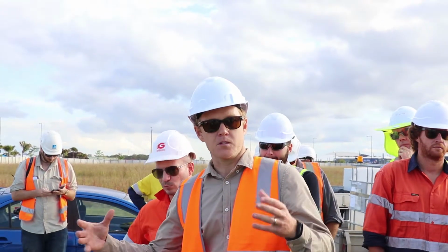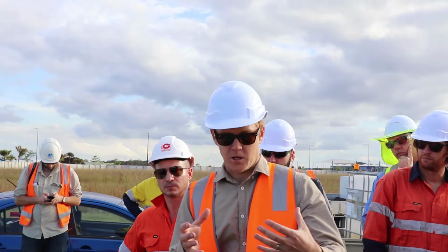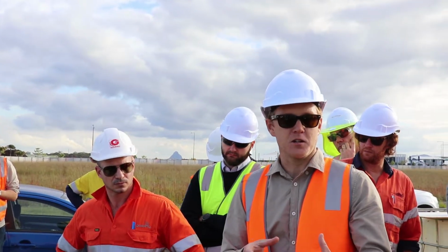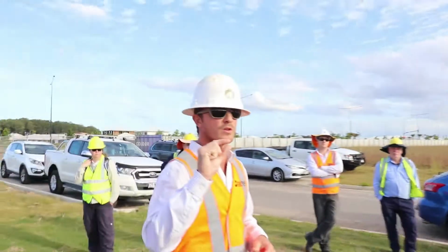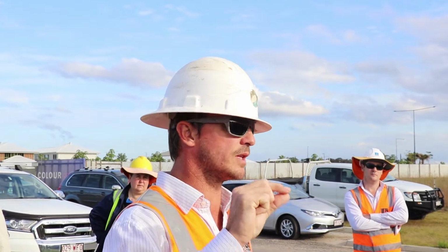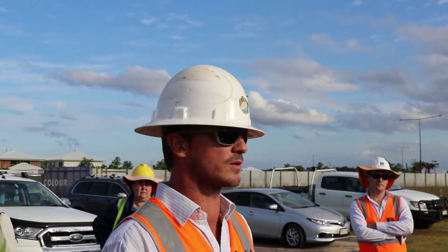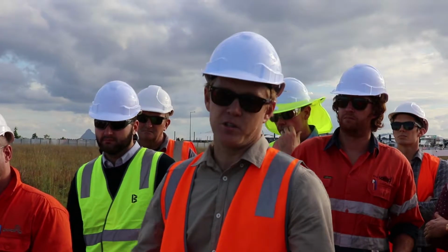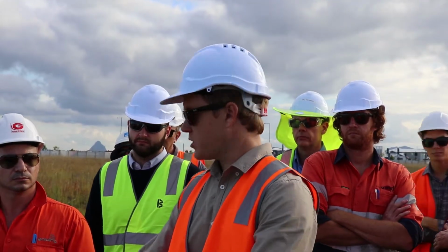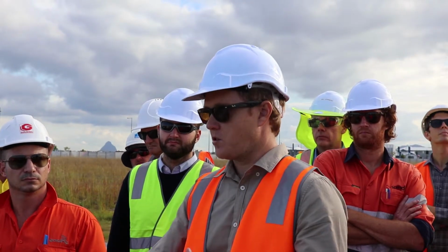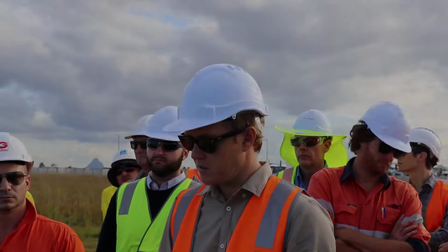Once you start getting bigger sites, maybe it's best to have 2 basins, or if you've got 10 hectares going down to an end-of-line structure, you probably want to know that end-of-line structure is very accurate and you might jump up in scale. Correct. Or if that window of opportunity is really quite tight for the products, then you need to make sure you're getting a system that's going to measure that flow as best it can to dose accordingly. It's all going to be risk-based. Smaller sites, lower risk. Simple, smart, cheaper systems are going to be the go. If you've got a very sensitive site, bigger site, you're probably going to have more money to play with to put in a more sophisticated system.